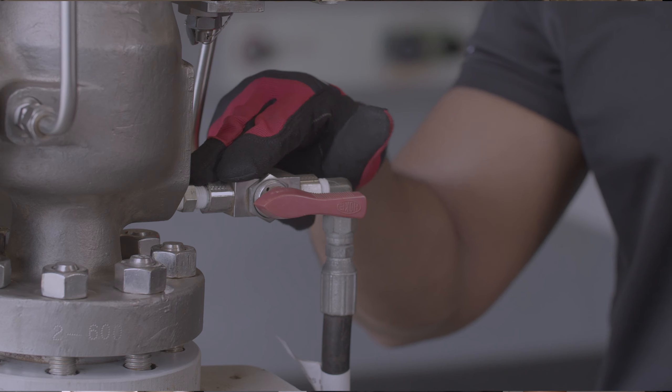I will then turn the 3-way ball valve from the integral sense connection to the remote sense connection. This transition will allow the true vessel pressure to be sensed by the pilot and the valve will immediately become stable. I'll show you that demonstration now.